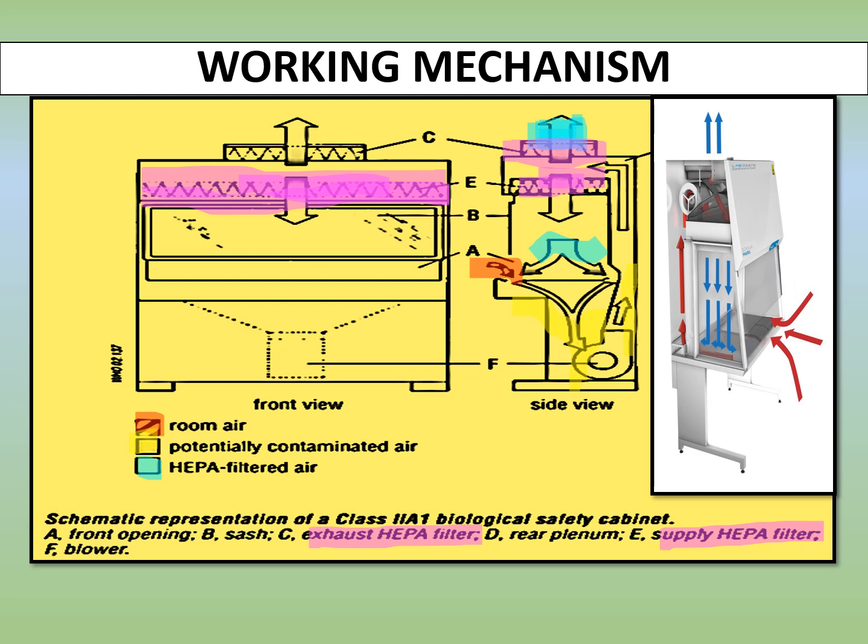There is a HEPA filter installed above the product, and this filtered air moves across the work surface, hence provides product protection. I hope you are clear with this concept.